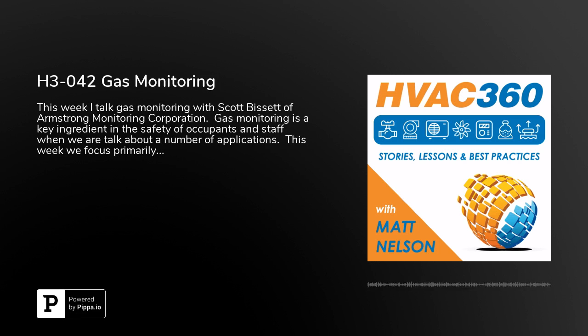Okay. Now, just to make sure I'm clear about this, does that mean up high in addition to a sensor in the breathing zone? No. Well, no. With ammonia, it's rare that we see a slow leak that'll settle in the breathing zone. It's going to leak and then it's going to go up. And the risk really isn't so much that somebody's standing over it when it's leaking. It's going to pool at the top of the space, and so we want to detect it as it pools. Okay, so basically, there's no problem about warming up, cooling down, anything like that. If ammonia leaks, it's going to go up.